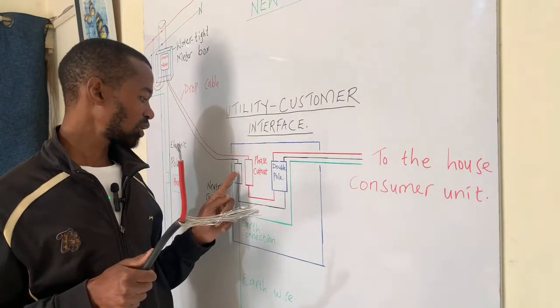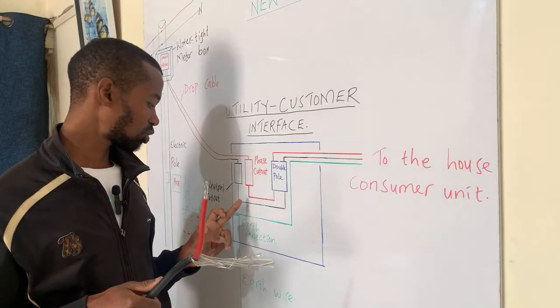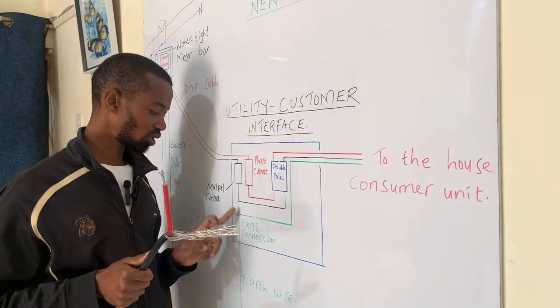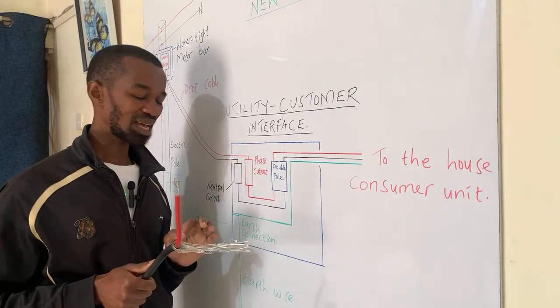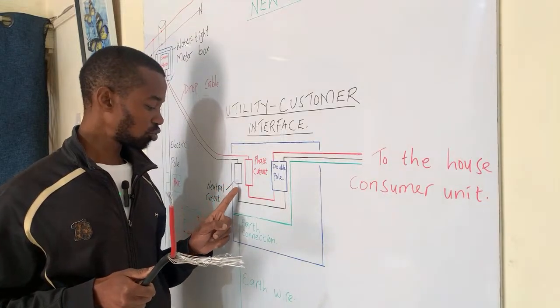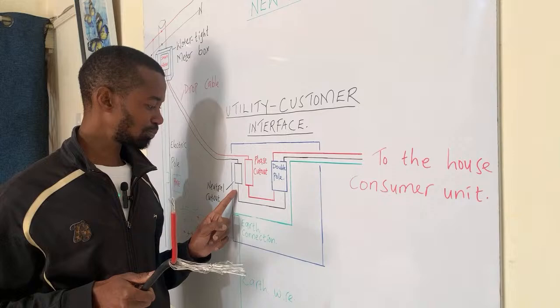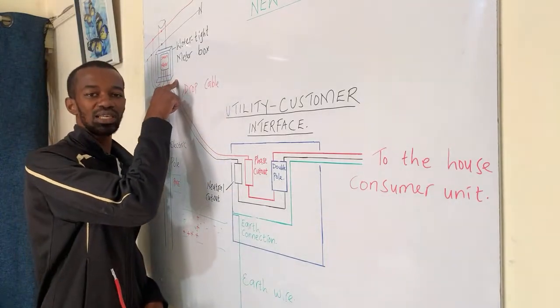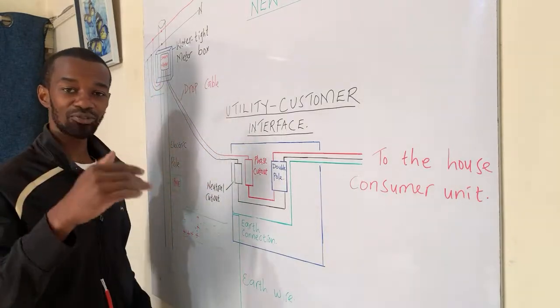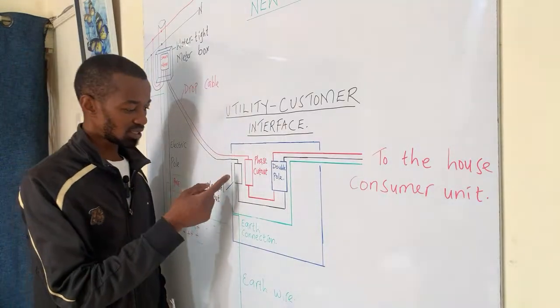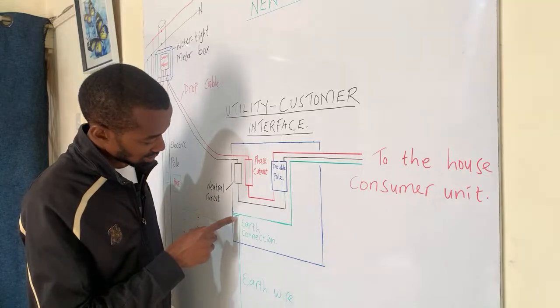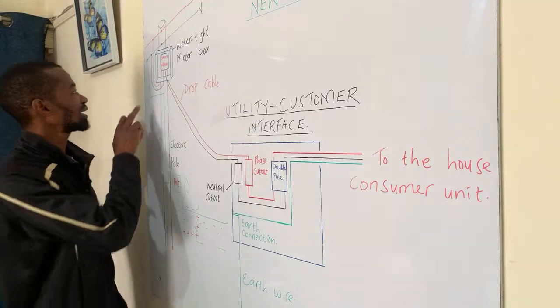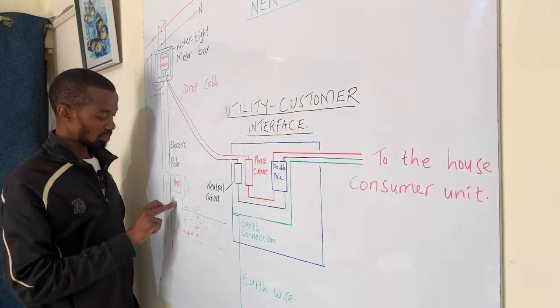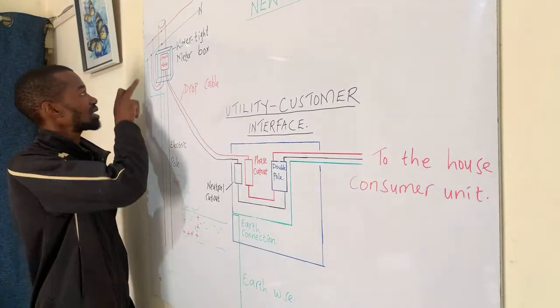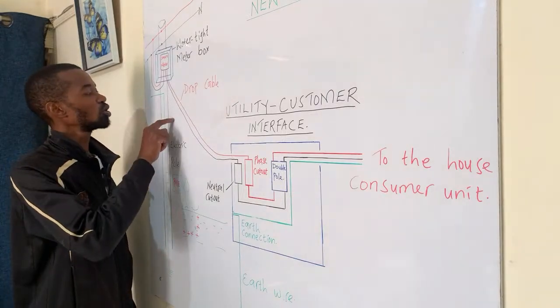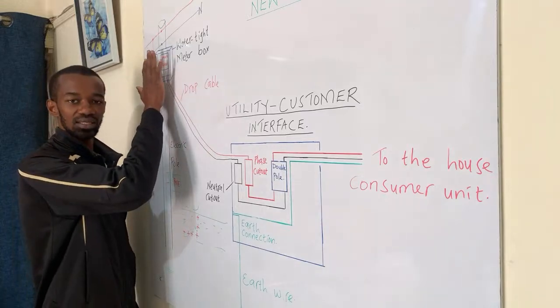So what we have been connecting is that some meters will be connected, and you will have to bond the earth connection to this particular point. Now, for the smart meters and many meters that are coming up nowadays, if you loop the earth and the neutral at this particular point, then the meter will start counting very fast. Remember, that is a bond that is done after the meter. And if you have already done the connection where you have the PME, standing for protective multiple earthing, connected at the neutral on the pole, there is no point in again looping the neutral after the energy meter.